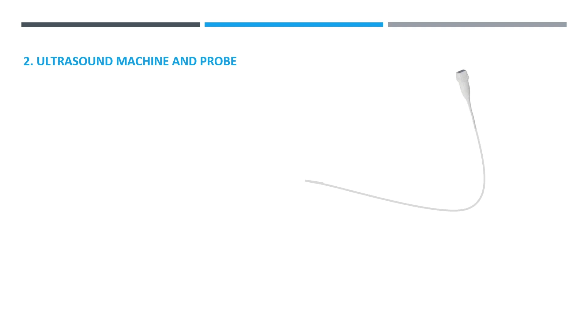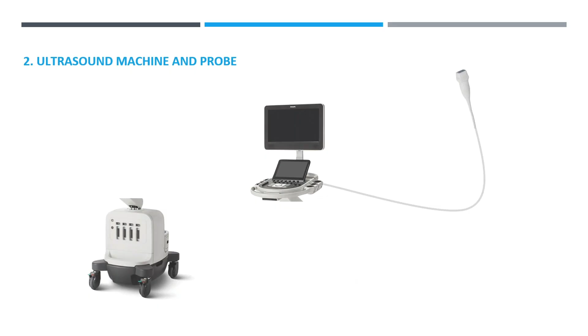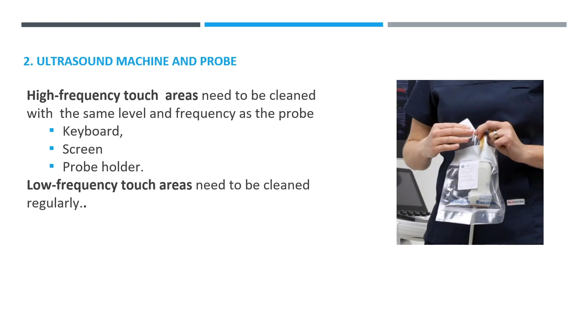And so what we've done in terms of providing guidance is we've really pragmatically made a decision to separate high frequency and low frequency areas of touch that warrant disinfection from low frequency areas. And our recommendations are as follows: that the high frequency areas, which are self-evident, it's the keyboard, the screen, the probe holder, etc., they need to be cleaned to the same level of disinfection and with the same frequency as that of the probe. Low frequency areas, such as the rest of the machine, they do need to be cleaned on a regular basis.